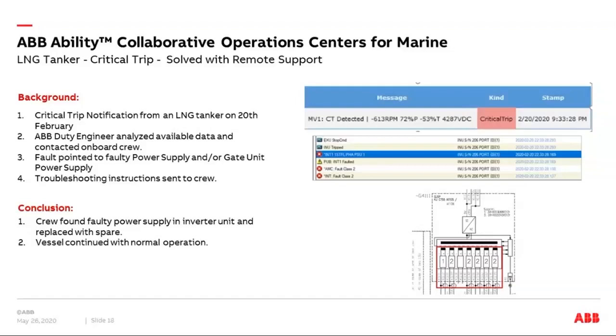So in this case, a critical trip notification was sent. The duty engineer analyzed available data based on the event list and the data loggers the system collected. It immediately pointed towards a faulty power supply, or gate unit power supply, in a medium voltage frequency converter.